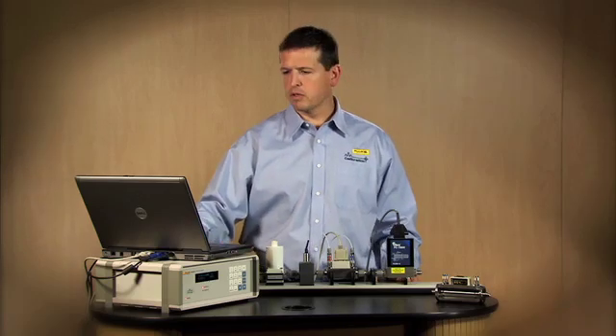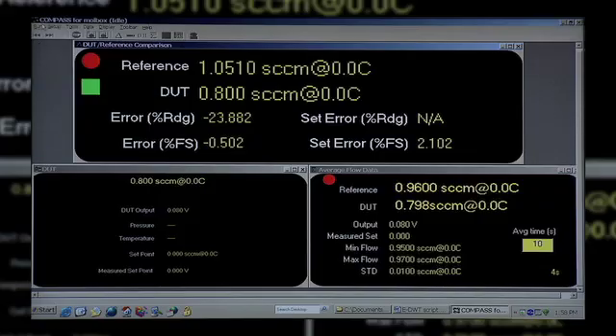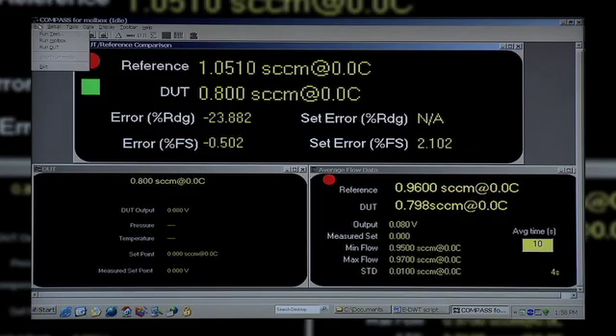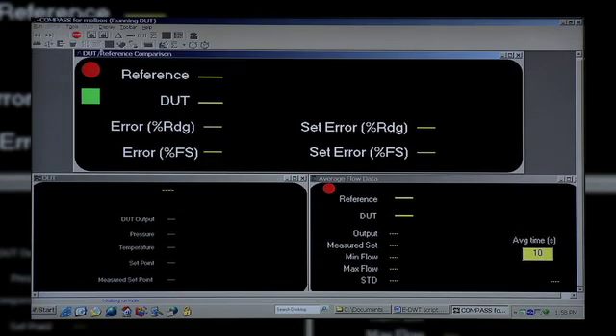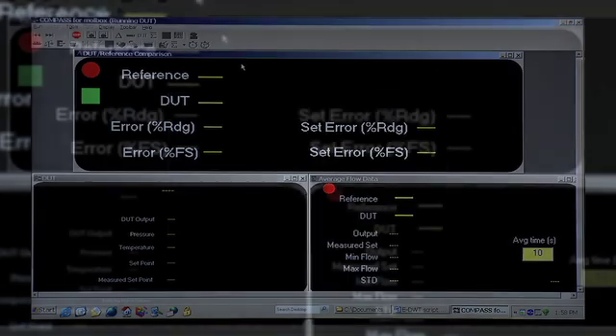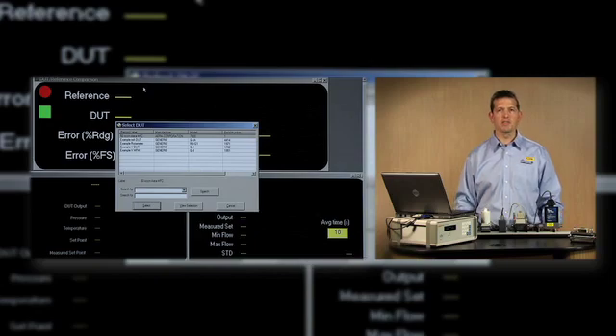For my adjustments I'm going to use Compass and its Run DUT mode rather than Run Test. Under the Run Manual I'll choose Run DUT. In this case it boots into a mode where we can take live real-time readings out of both the device under test and the molebox and adjust the MFC to match the molebox reading.